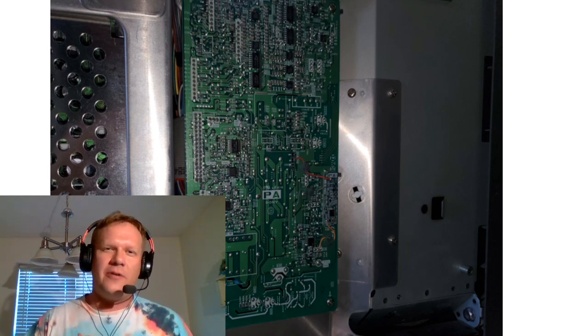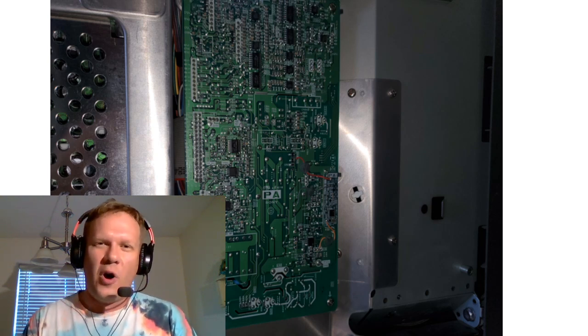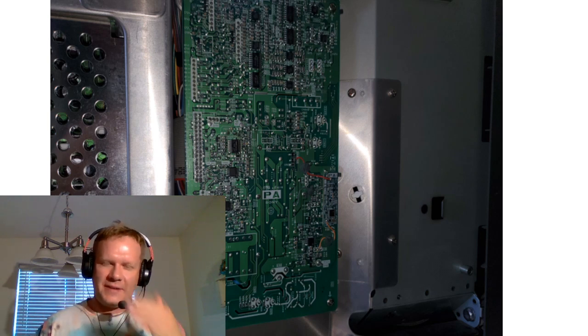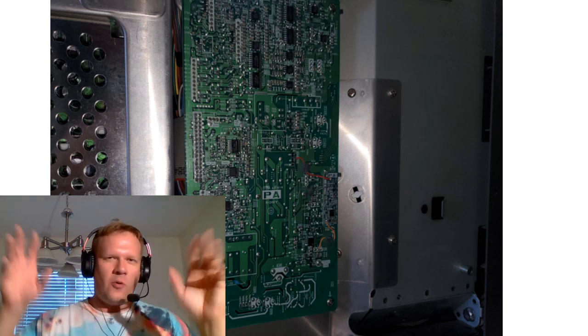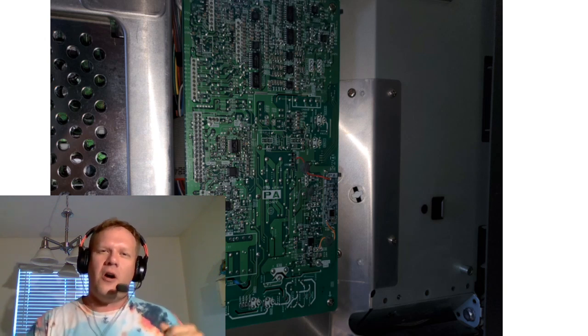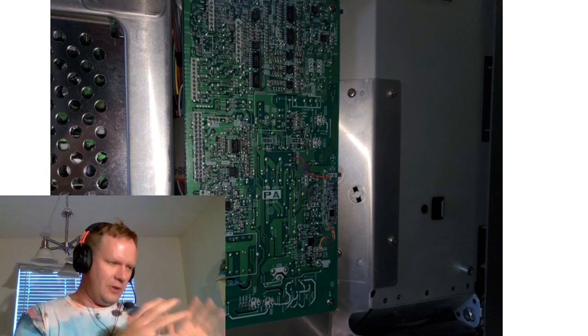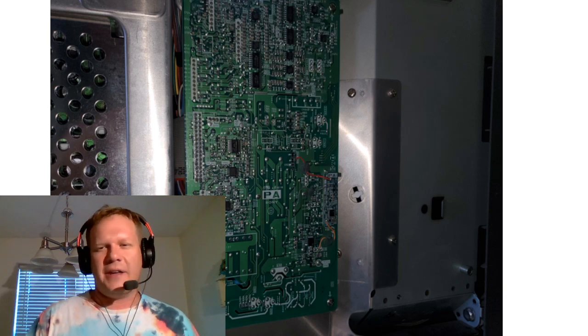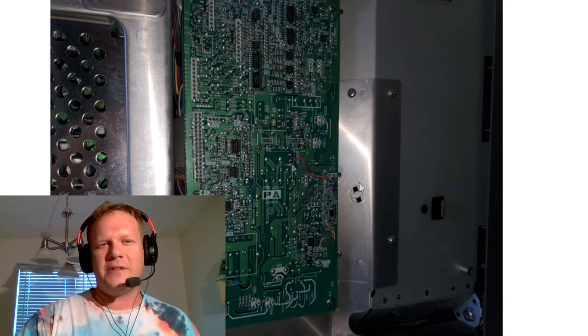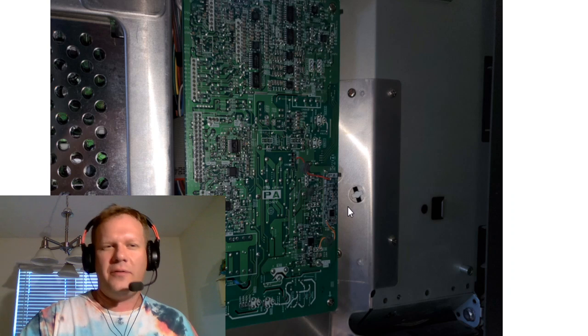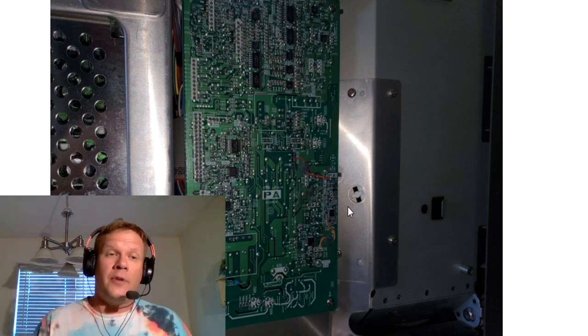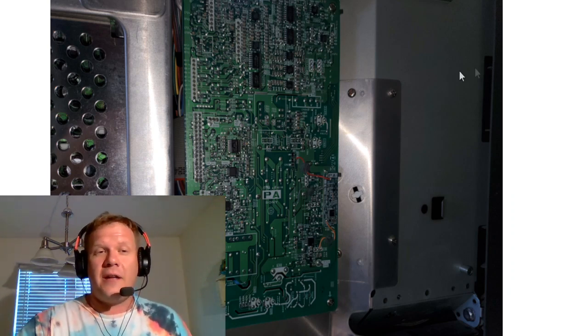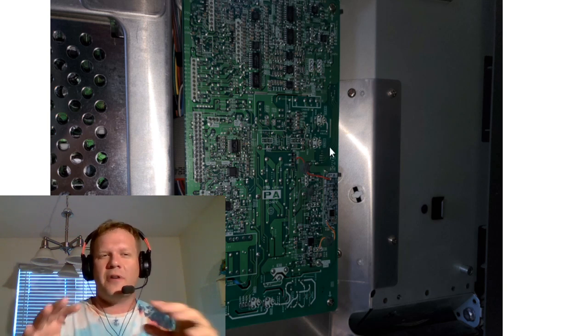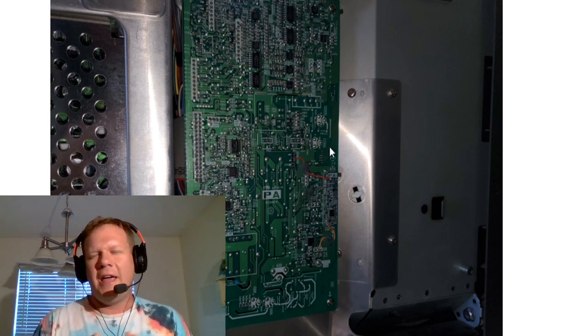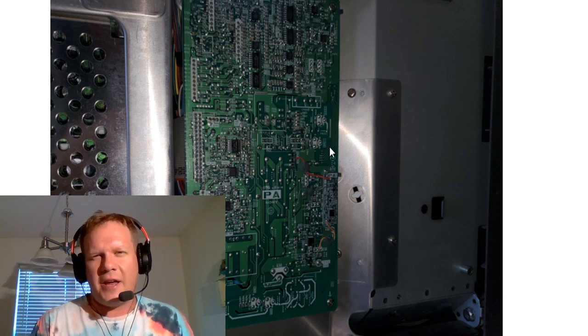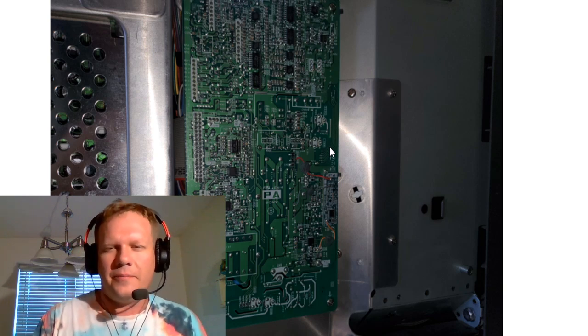Definitely check this out, look into it a little bit more. If you own one of these monitors, it's really simple to get to this side, just four screws and pop this plate off on the left-hand side of the monitor when you're looking at the screen. You could check and see right there without doing anything else, see if you've got this daughter board installed. If you do, it's probably a good chance you have a newer tube installed. Then you could check out the back of your tube and make sure it looks like that, because if it looked all nice and factory standard, I wouldn't have thought the tube would have been changed, I would have just thought it was on its original one.